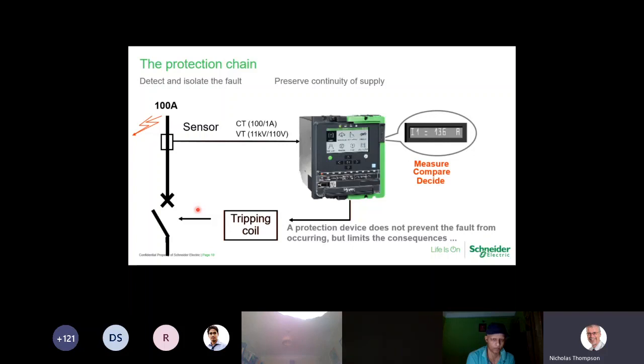Occasionally, because of various things within the circuit breaker, it might be age, or it might be a very poor environment for the circuit breaker to be working in, i.e. a rail environment where you get a lot of dust and muck, the circuit breaker may actually fail to trip, sticking closed. Therefore, in these circumstances, we would ultimately need the circuit breaker above that to work. And if that one fails to work, then we would need the one above that one to work. So this is why we need the ones in the whole system to be able to work and protect the one downstream of the fault.